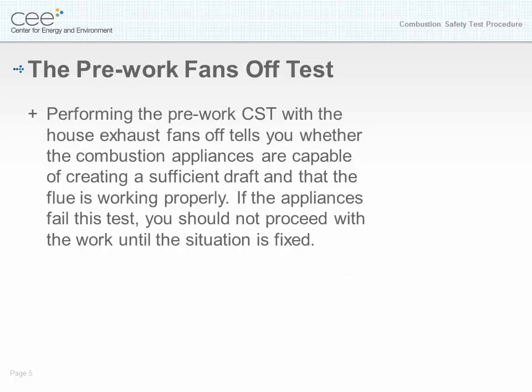The pre-work fans off test. Performing the pre-work combustion safety test with the house exhaust fans off tells you whether the combustion appliances are capable of creating a sufficient draft and that the flue is working properly. If the appliances fail this test, you should not proceed with the work until the situation is fixed.